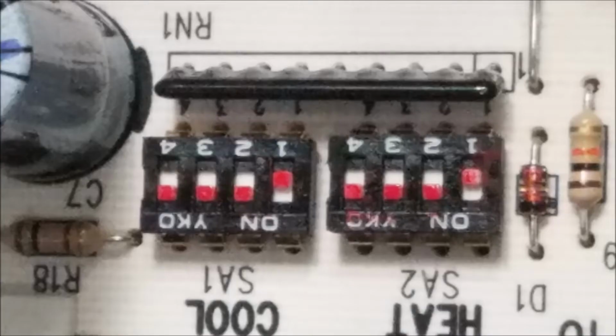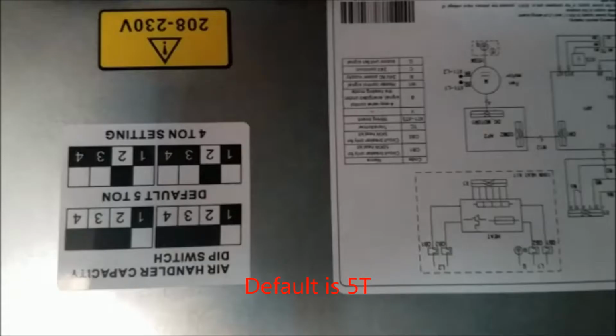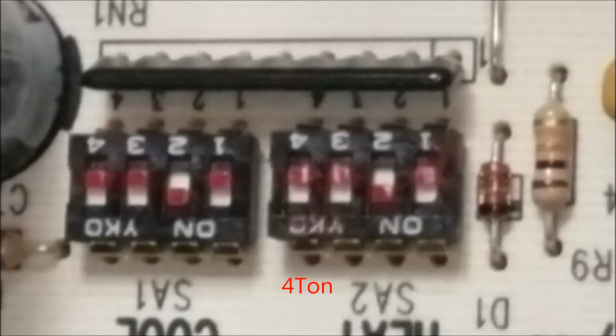It went together smooth. As I stated previously, my dislike was the configuration settings. If you rotate the panel, you can kind of see the switches are in that orientation, but again, this should have been done better. So I'm showing the 5-ton here, which is shipped with, but this is really 4-ton. So as you see the switch settings on the left, that's what I have when I rotate the cover here on the actual switch settings for the heat pump. And again, that could have been done better, but I'm still happy with the unit.